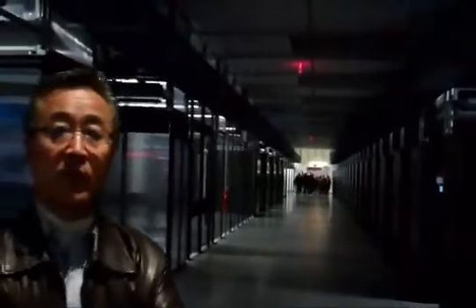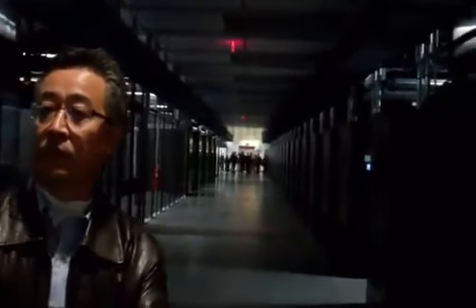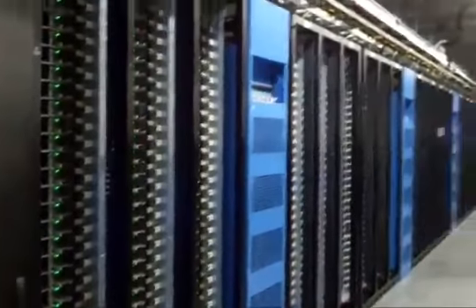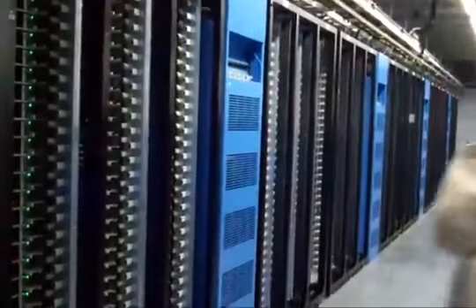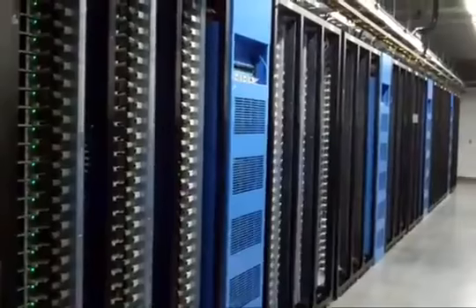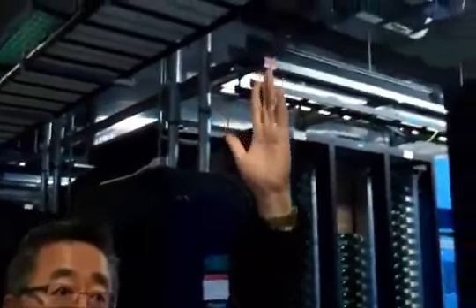Okay with photos? Yes. Right now we're running at about 72 degrees. As you can see, the cold air is coming down from the penthouse through this shaft. In the entire data center, we do not have ductwork. There's no supply air duct or return air duct.